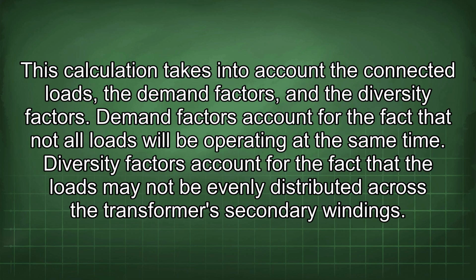This calculation takes into account the connected loads, the demand factors, and the diversity factors. Demand factors account for the fact that not all loads will be operating at the same time. Diversity factors account for the fact that the loads may not be evenly distributed across the transformer's secondary windings.